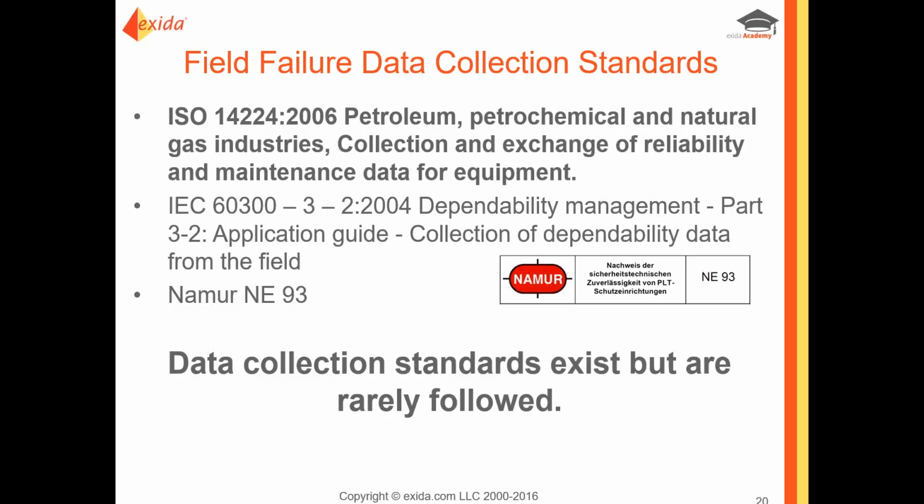There are data collection standards. There's ISO 14224, and I'm told a new version is just about ready to be released. There's IEC 60300-3-2, and of course in Germany they have an NE93 standard. And I'll have to say that in looking at all of these, the ISO 14224 standard stands out as probably the best of all the standards I've ever read for data collection methods. So if you're going to have to buy one, I recommend the ISO 14224 as something you should look at first.